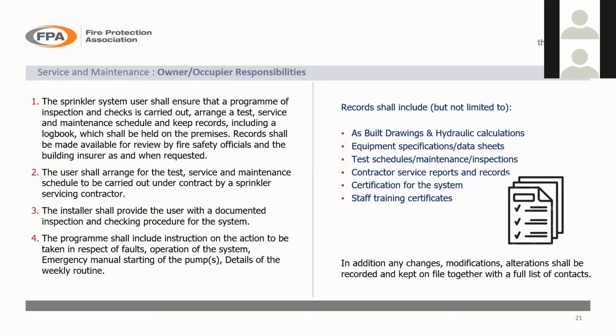So the user shall arrange for the test, service and maintenance schedule to be carried out under contract by a sprinkler servicing contractor. So there are limitations to what the user can do, and then you need to turn to the services of a sprinkler servicing contractor to get the system maintained throughout the year. So the installer shall provide the user with a documented inspection and checking procedure. It will include instruction on the actions to be taken in respect of faults, operation of the system, emergency manual starting of pumps, and details of the weekly routine.